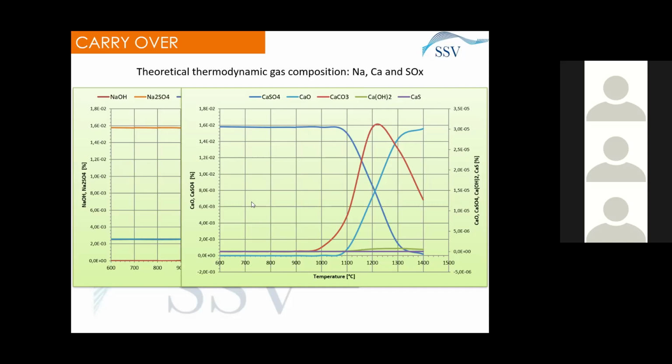air. Also, yes, it depends on the type of color and the amount of raw material you are using. If you are using more cullet, you can have a flame with a higher velocity, because there is less impact of the carryover. There are many aspects. In our experience, it is something we do in the field with measurements, and we start from what we find at the moment in the plant, and then we start changing the inclination of the burners, following some principles, but then after this it is all about what we see in the field. I hope that answers your question.